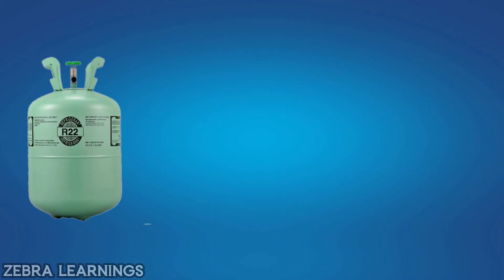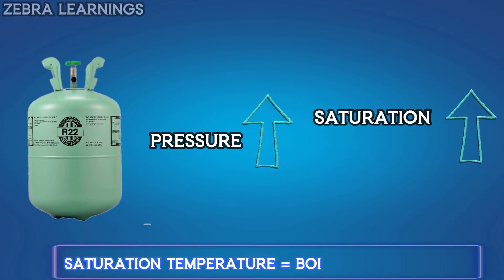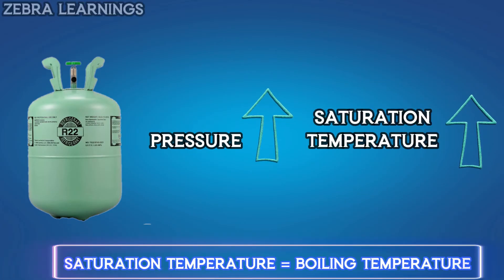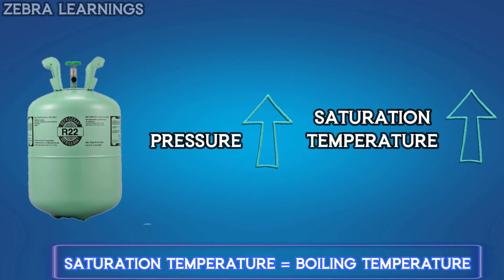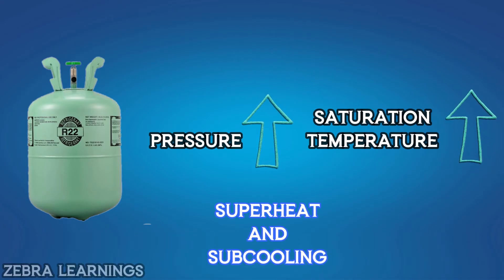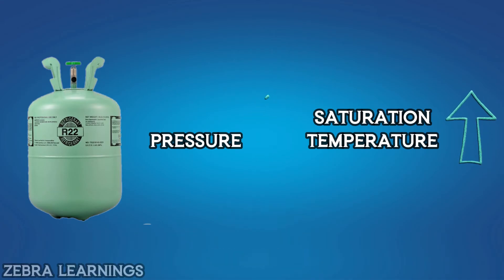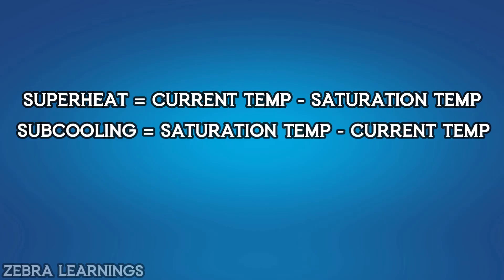The same concept applies to refrigerants: as pressure increases, the saturation temperature of the refrigerant also increases. The saturation temperature of a refrigerant is helpful in detecting the values of superheat and subcooling. Superheat equals current temperature minus saturation temperature. Subcooling equals saturation temperature minus current temperature.